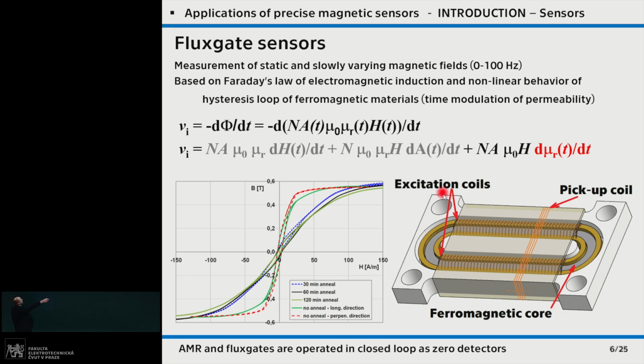We have a ferromagnetic core, in this case this racetrack shape, and we have some excitation coil. When we run a current through the excitation coil, when the amplitude is small, we are in this part of the loop, so the permeability of the core is high - it can be several hundred thousand typically. So when there is some external field, the flux lines of the field are concentrated into the core. While when we are in the saturation part of the core, the permeability is equal to 1 basically, and the core is virtually invisible to the external flux.